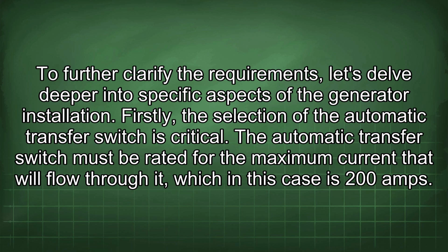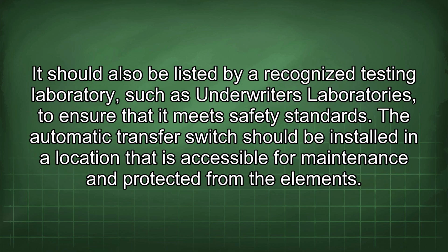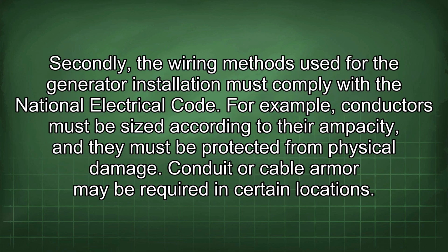Firstly, the selection of the automatic transfer switch is critical. The automatic transfer switch must be rated for the maximum current that will flow through it, which in this case is 200 amps. It should also be listed by a recognized testing laboratory, such as Underwriters Laboratories, to ensure that it meets safety standards. The automatic transfer switch should be installed in a location that is accessible for maintenance and protected from the elements. Secondly, the wiring methods used for the generator installation must comply with the National Electrical Code.